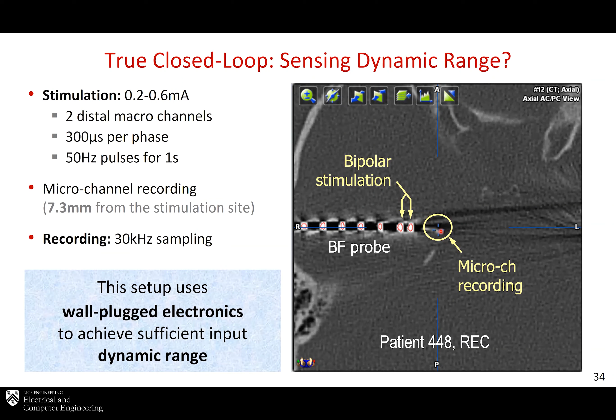And then what we do is we increase the amplitude of stimulation and see what is the required amplitude on the recording site so that we can have a full signal plus artifact. And you have to keep in mind that when you do this with existing clinical equipment, those are wall-plugged instruments which have no power limitations. And we're trying to develop a technology that can handle this with implantable microwatt level power. So here is what I described. You are increasing the amplitude of stimulation 0.2, 0.4, 0.6 milliamps and further. And you can see in blue is the signal plus artifact.